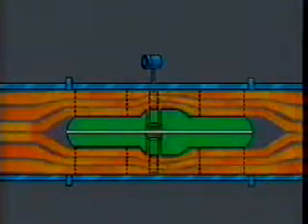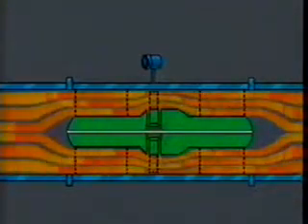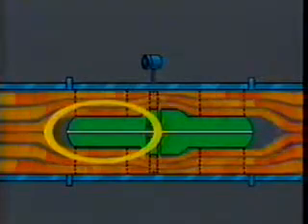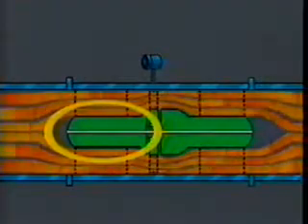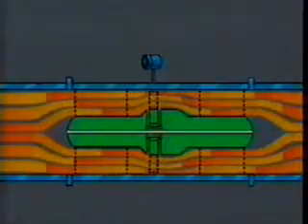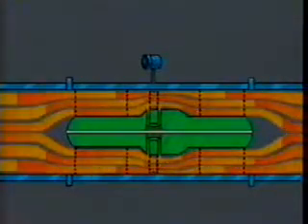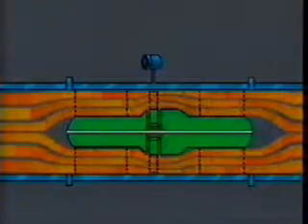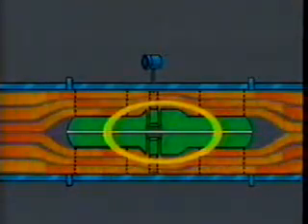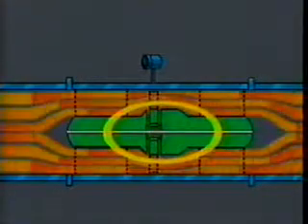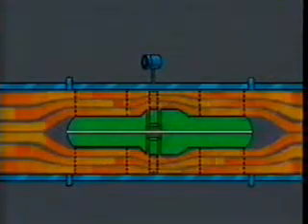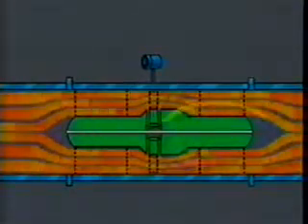Now, this floating occurs as liquid entering the meter is deflected outward by an upstream cone, which increases its velocity and causes a slight pressure drop. After passing the turbine blades, the flow is redistributed. Because the rotor hub is larger than the upstream cone, some of the fluid flows directly over the hub. The rotor then floats in balance between the upstream cone and the downstream cone.